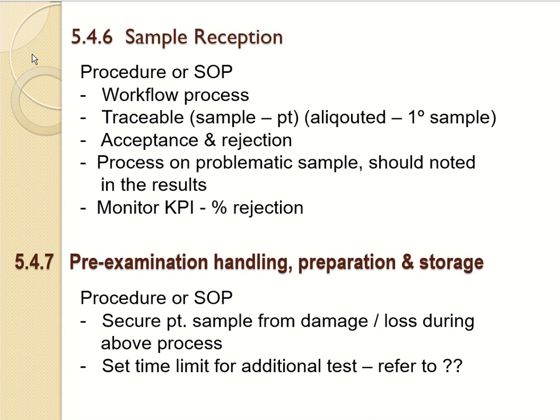Under clause 5.4.6, sample reception, the lab shall have a procedure or SOP for the workflow process, and traceability, such as the traceability of the sample to the patient and the aliquots traceable to the primary sample. It should also cover the acceptance and rejection process for problematic samples, which should be noted in the results, and should monitor the KPI, the percentage of sample rejection.